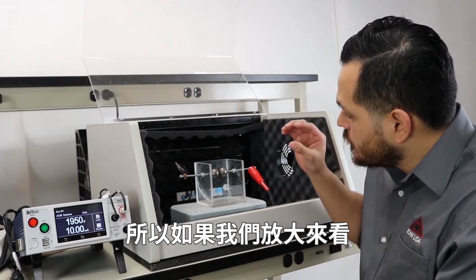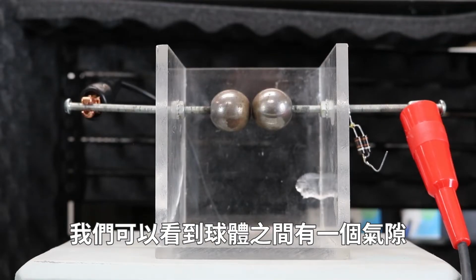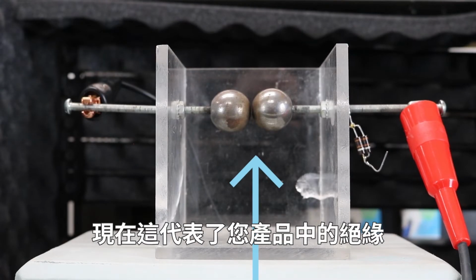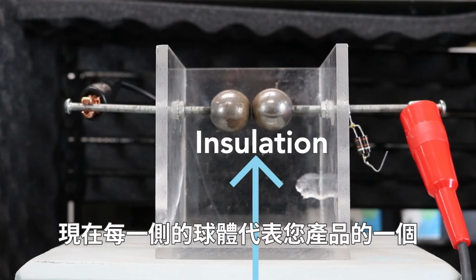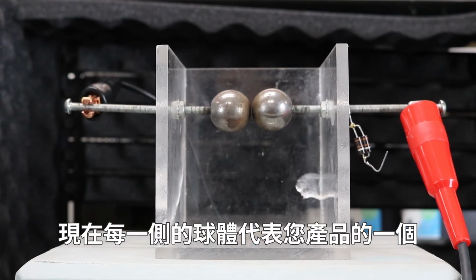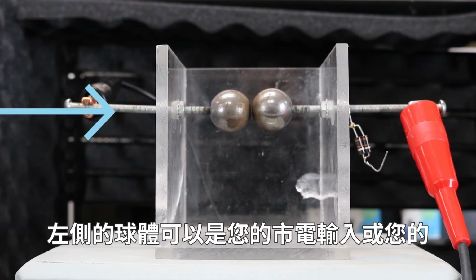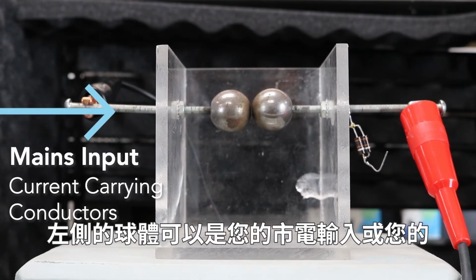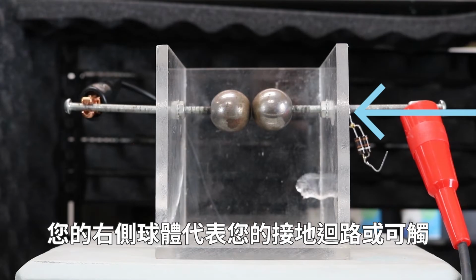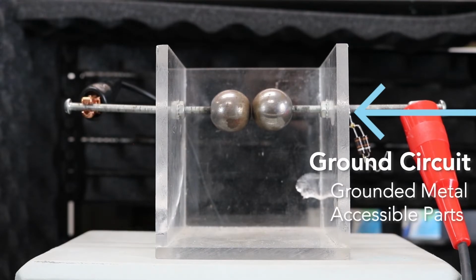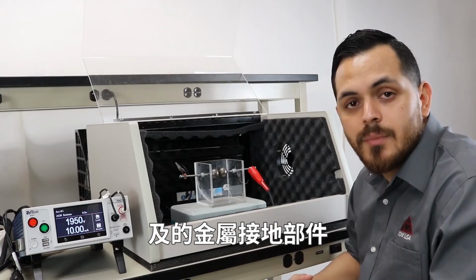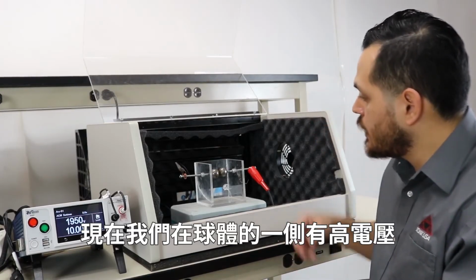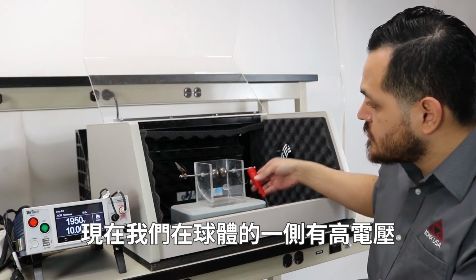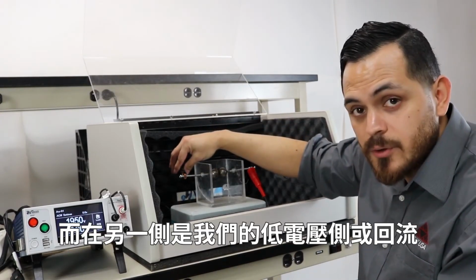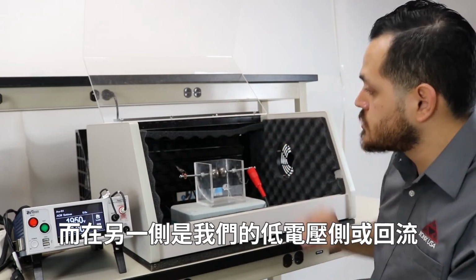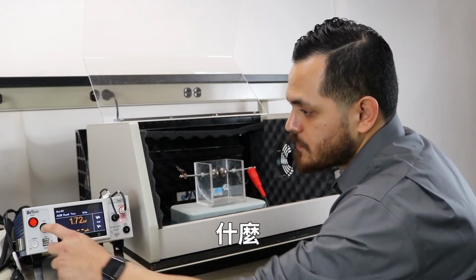So if we zoom into this, we can see that there's an air gap in between the spheres. Now that represents the insulation in your product. Each sphere on each side represents a circuit of your product. The left sphere can be your mains input or your current carrying conductors, while your right sphere represents your ground circuit or your grounded metal accessible parts. Okay, now we have high voltage on one side of the spheres and our low side of the voltage or the return on the other. So now let's see what happens when we start a test.